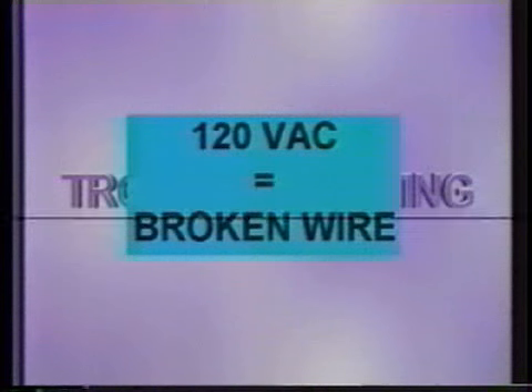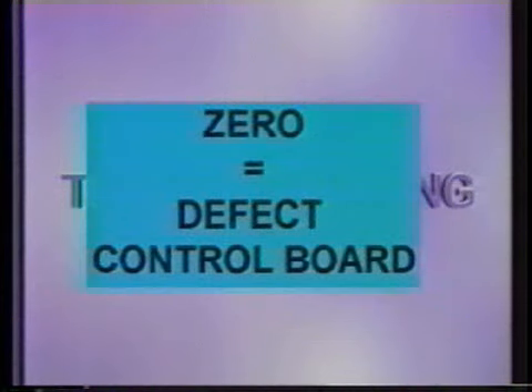If we have 0 volts, then we have to go back to the control panel. And here we want to measure the voltage drop between pin 7 of the 10-pin plug and neutral. If we have 120 volts, we know we have a broken wire to the dispenser. If we have 0 volts, we know we've got a bad control board.